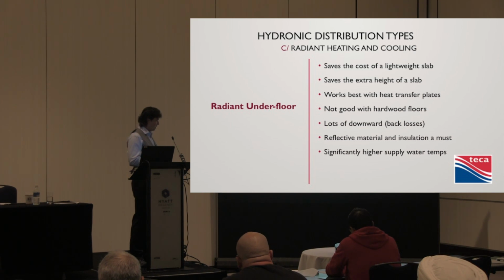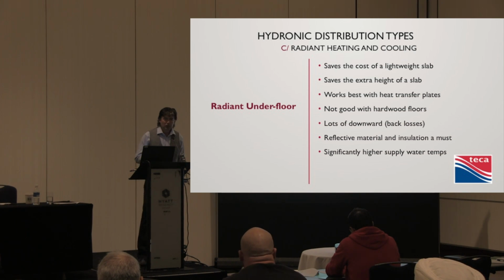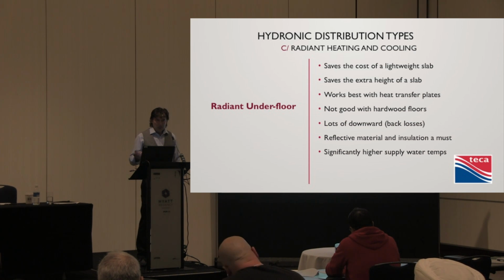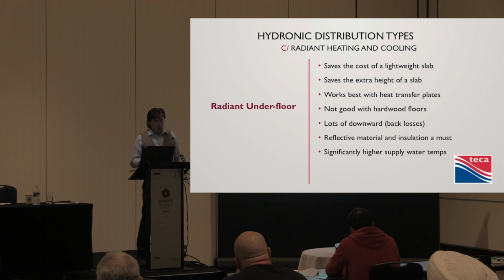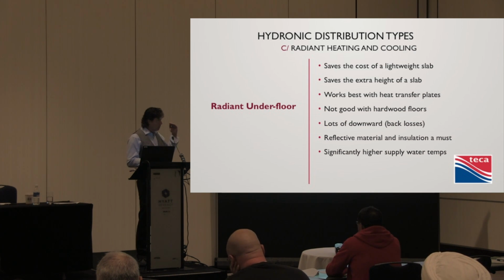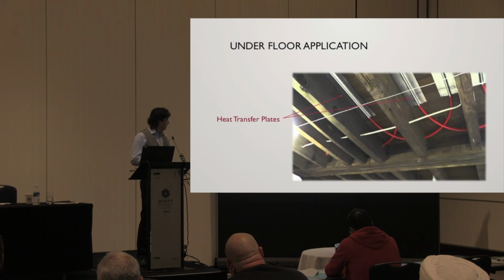Again, that works best with heat transfer plates, and I'll show you that in a minute. Is it good with hardwood floors? I guess it depends. I shouldn't say it's not good with hardwood. Depends on your hardwoods. Again, you guys would know better than I do, but I think engineered floors have way better resistance to high temperature heat, because when we're heating underneath the floor, we're having to heat through a subfloor, so we're circulating higher water temperatures. Because we're heating in a joist space, usually, we've got a lot of downward losses, so we're heating below as well. So we have to take care of that with some insulation and reflective material. Significantly higher water temperatures. There's just no getting away from that. We'll talk about that here shortly.